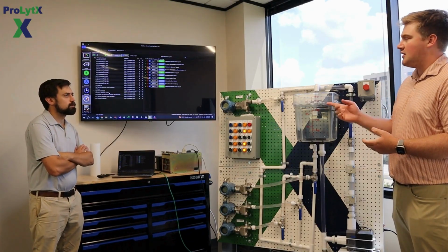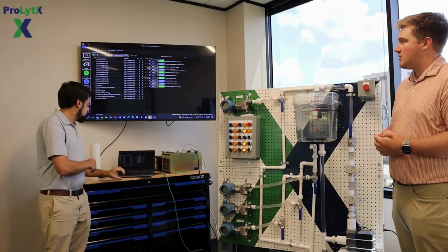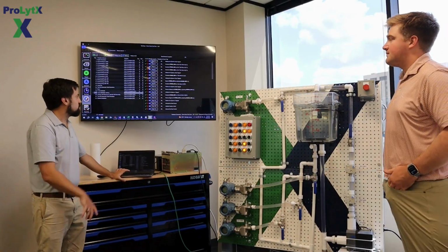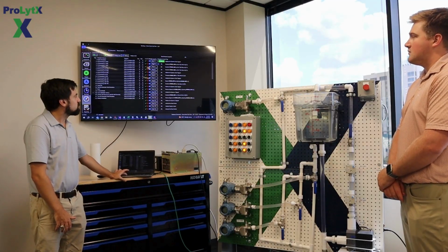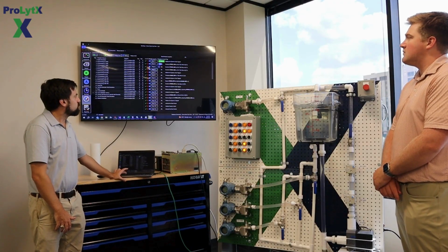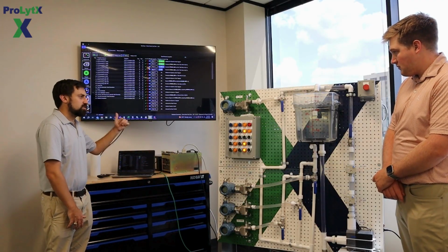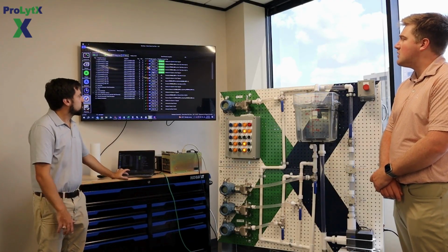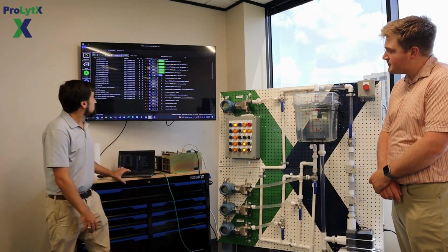Do you have another voting combination we can show within the test drive? Yeah, I can give you a quick 2-out-of-3 on the level as well. It starts the same way, so we confirm that the system's not tripped. Again, we'll simulate everything to just before it trips at 81. Here we're going to be tripping at 79%. So we confirm that everything's pre-tripped at 81, and then validate we're not tripped. Then we're going to simulate A to trip. See the light come on, there it is.